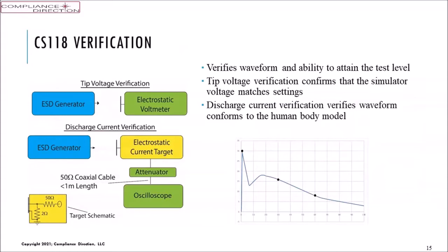CS118 or the ESD verifies the waveform and the ability to attain the test level. The top part, the tip voltage verification, is simply an air tip that's charged up. We bring it into the range for the electrostatic voltmeter to measure the voltage appearing on the tip. It should be what the dial on the generator says. Then we apply the discharge current waveform as a conducted waveform into a target.